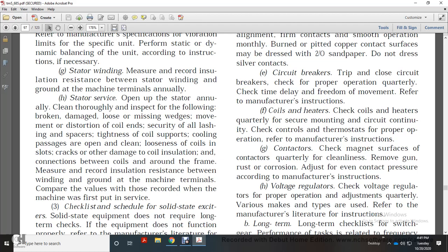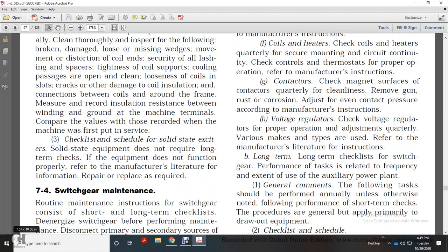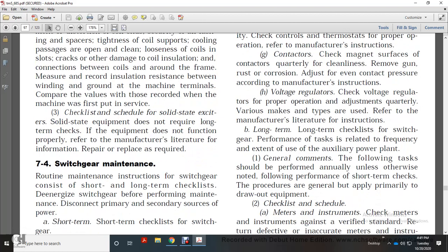Measure and record insulation resistance between winding, ground, and machine terminals. Compare the value recorded with the machine when it was first put in service. Checklist schedule of solid excitation and solid state. The equipment is not required for the long-term check. With equipment that does not function properly, refer to manufacturer literature for information; repair or replace as required.